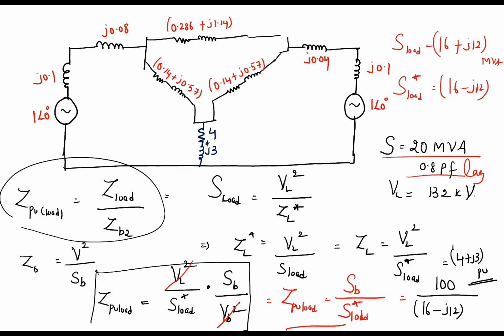This is how you simplify the load. To calculate the per unit impedance of the load, you simply have to remember S base divided by S load conjugate. Then you can calculate the per unit impedance of the load. So we have calculated this value as 4 plus j3 per unit. Okay. This is one of the typical questions on conversion. If you understand this question, you can do any conversion. Okay.